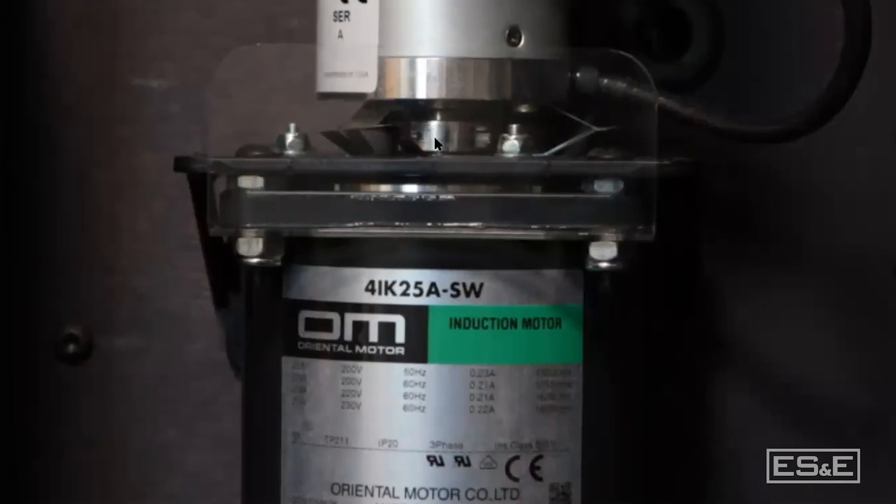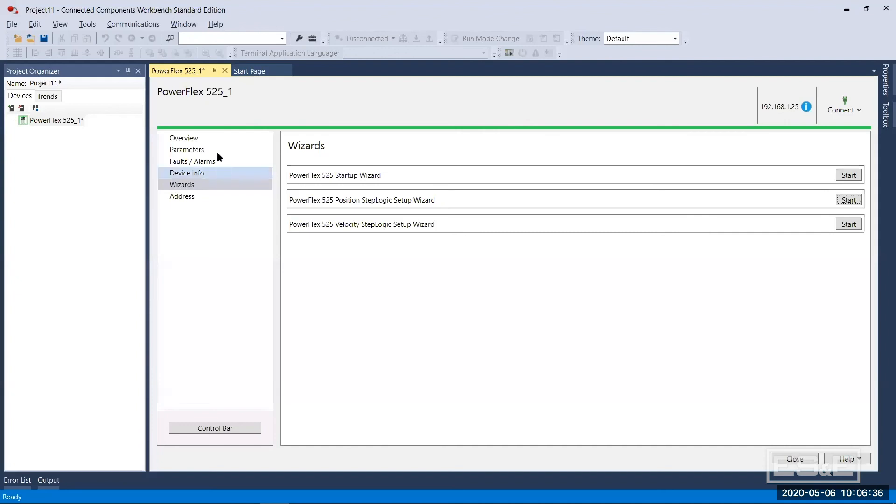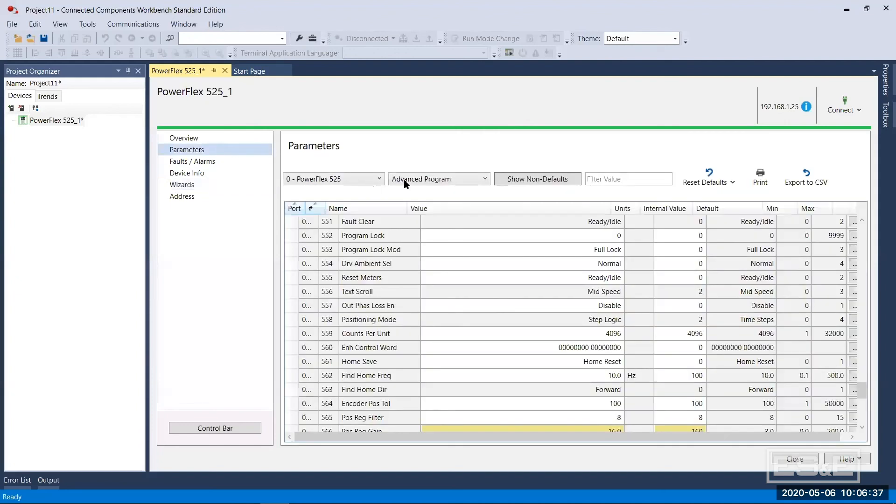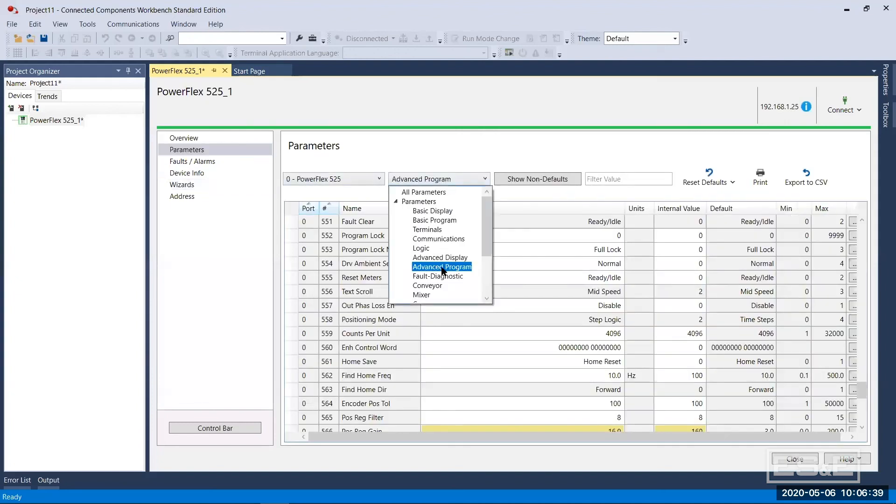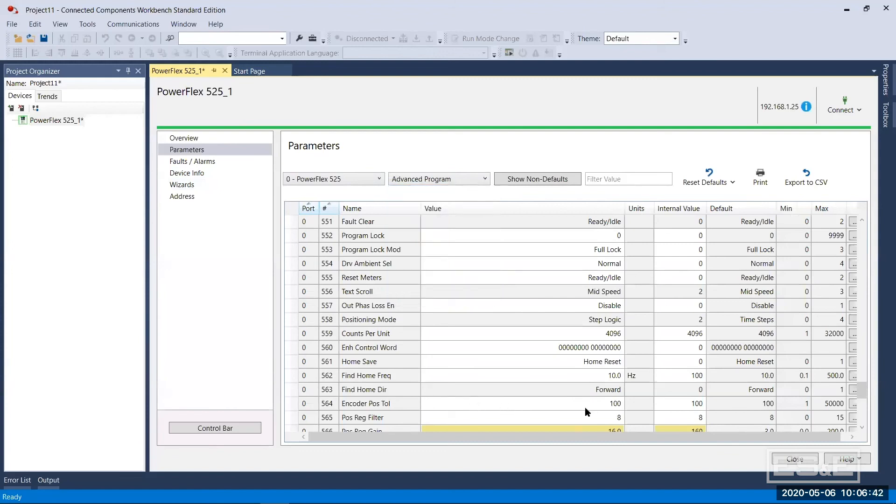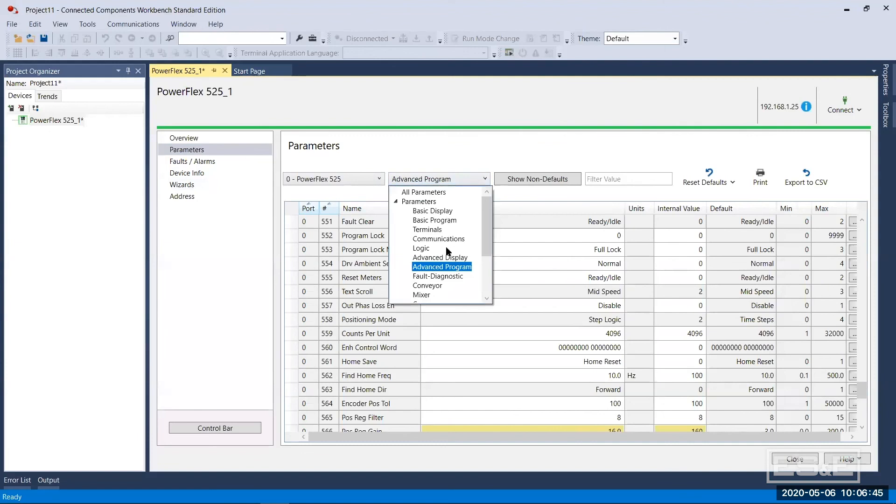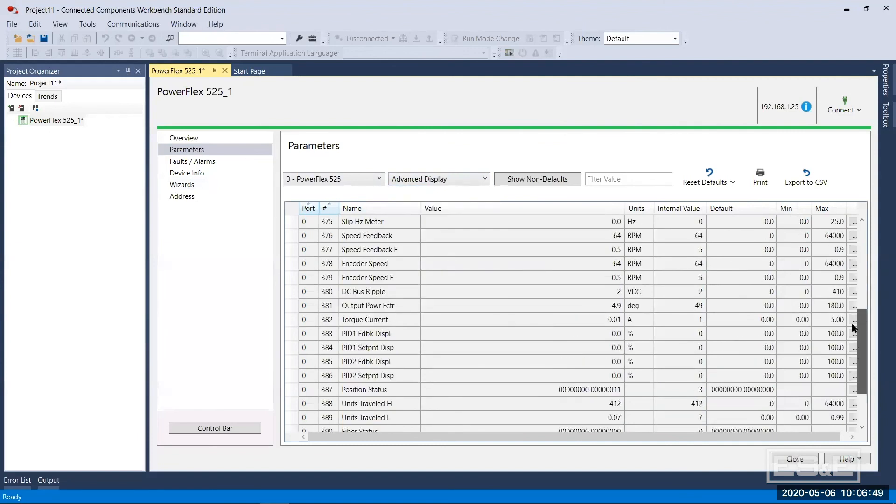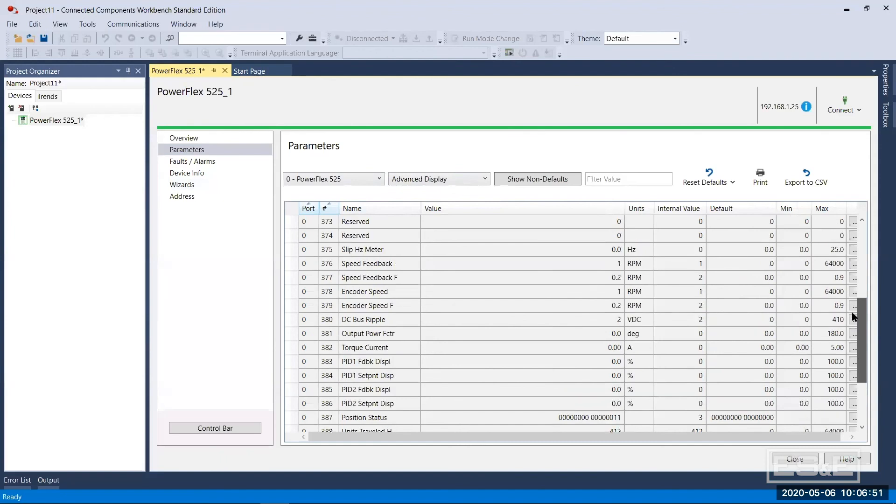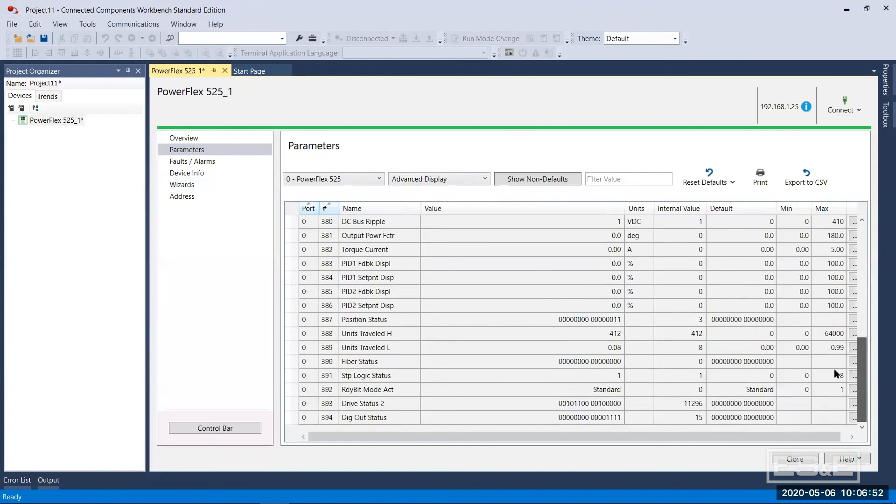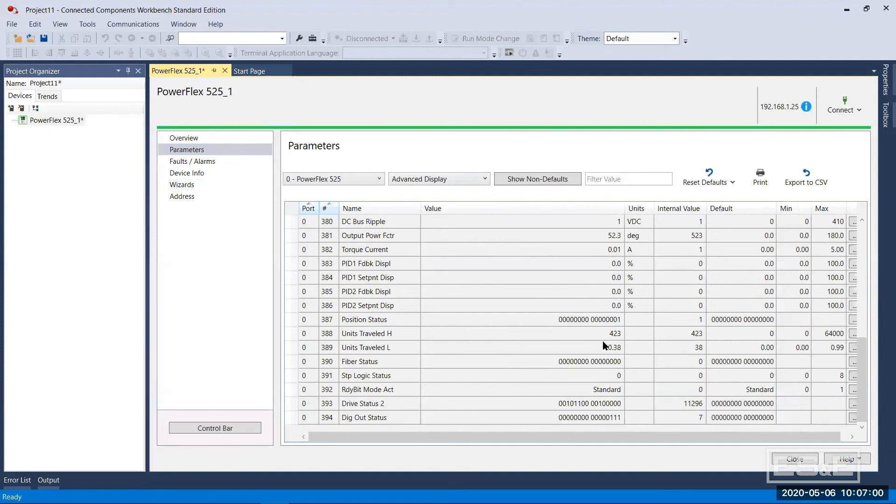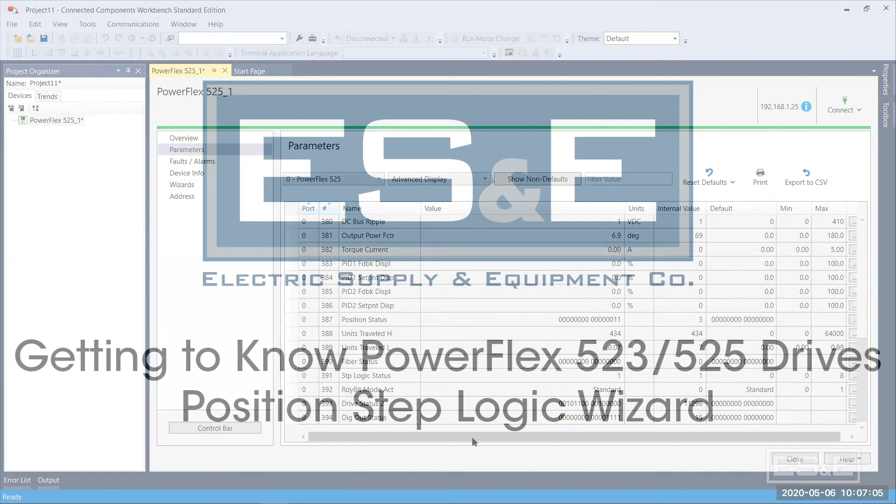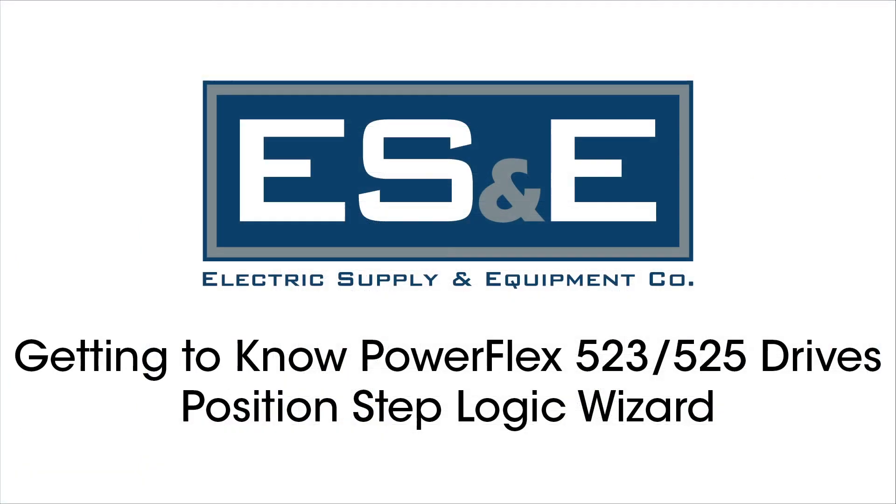For simple applications, if you need to do some rudimentary positioning, as you can see my encoder tolerance was set at like I think I had it set at 100. Let's go back to that parameter list under advanced. My encoder tolerance is set at 100 counts. Now let's go back to advanced display and you can actually look at my encoder units travel. You can see it increment and it should go to 424, now it should go to 434.